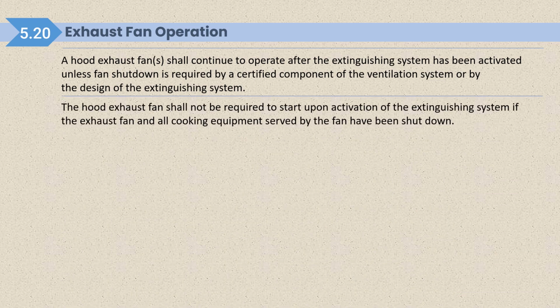The hood exhaust fan shall not be required to start upon activation of the extinguishing system if the exhaust fan and all cooking equipment served by the fan have been shut down. So it is not required upon activation of the extinguishing system if the exhaust fan and all cooking equipment served by the fan have been shut down. If all equipment are shut down, then it should not be required to keep running during the extinguishing system activates.